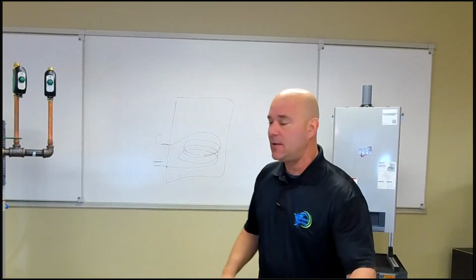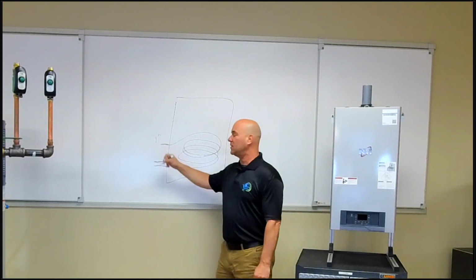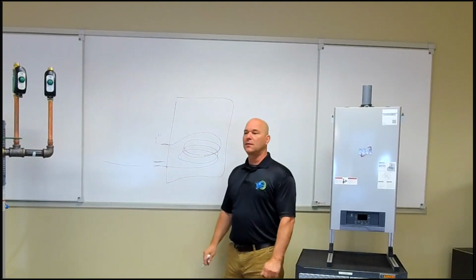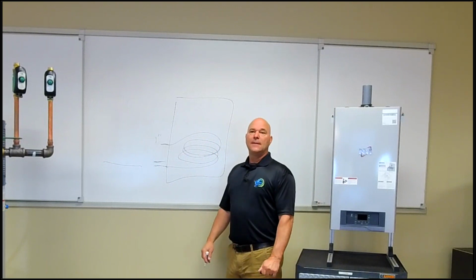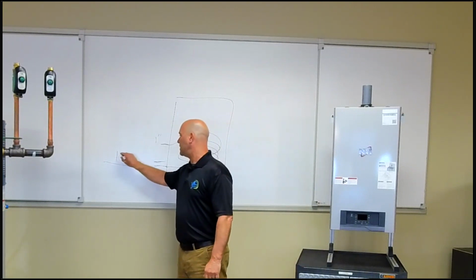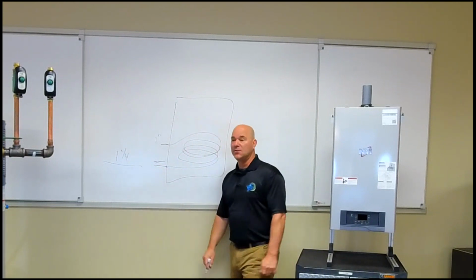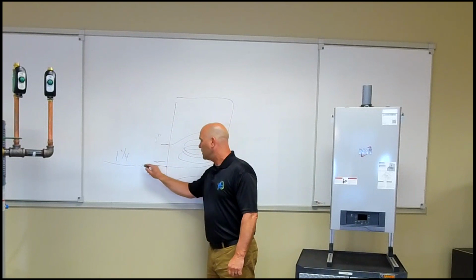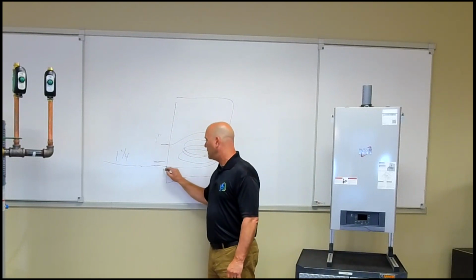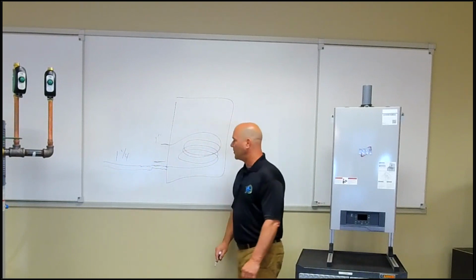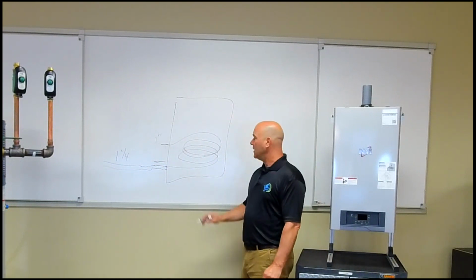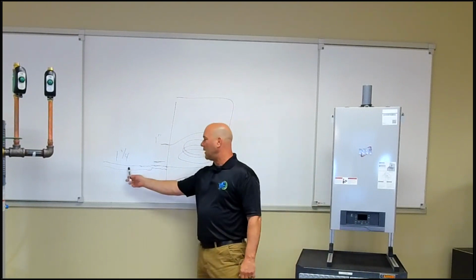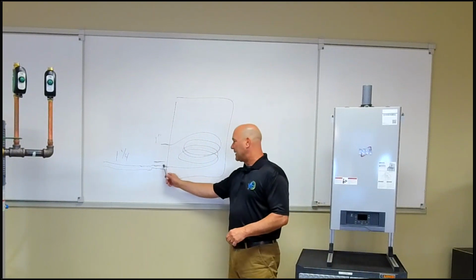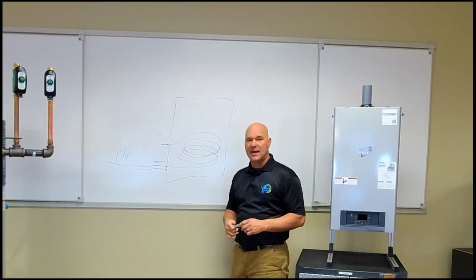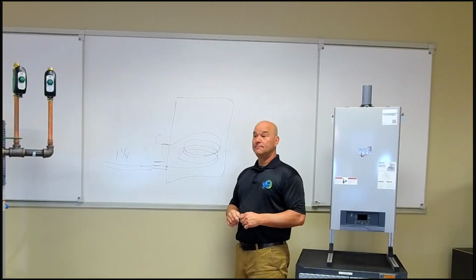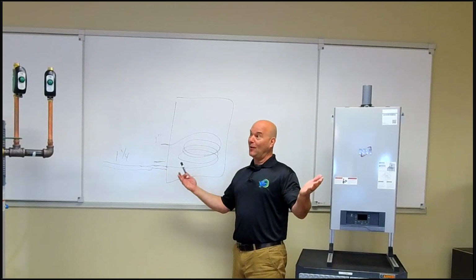So back to your pipe chart, what size, or get me real close, what size would the piping here from the boiler, the heating plant, what would it be? Somebody will see it in a minute, but I'll tell you it's 1.25 inches. And then when you get right here to this point, this is where your reducer would be. Okay? There, 1.25 inch pipe. Again, terrible drawer, but you get it. So how can I take the flow rate and the BTU from 1.25 inch pipe, neck it down to 1 inch, and not create velocity noises? Very carefully. I don't know.